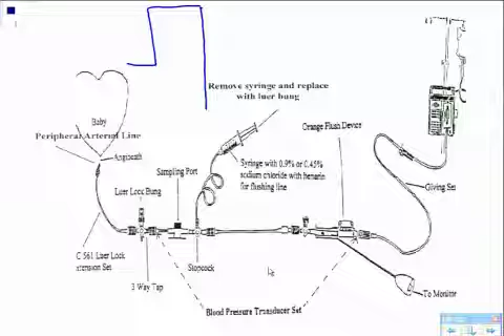Okay? Which means that the system that we have is that we make the tubing very thick. So if you take an A-line and bend it, does it ever kink? Very infrequently. You have to really force it to kink it. So A-lines are made extra thick, so the wave that comes at it through the A-line doesn't get dissipated into the environment. It goes directly to the transducer. But they tend to make it too rigid, okay, which makes it hyper-resonant. And when you have a hyper-resonant system, it's like taking a bell and making it a high-quality bell. If you just touch a bell that's good quality, you'll hear it ring multiple times, more than the impact that you hit it with. Okay, it's called hyper-resonance.